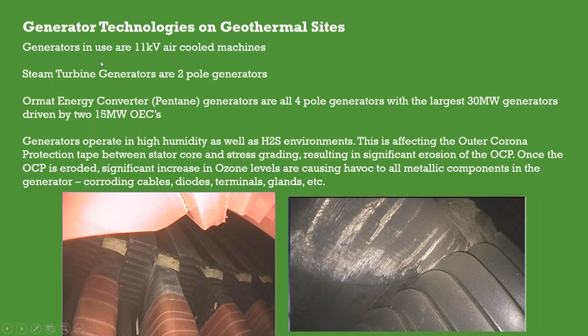The generators used in these geothermal plants are all 11 kV, air-cooled machines. The generators connected to the steam turbines are 2-pole generators, but the pentane OECs, or Ormat energy converters, use 4-pole generators. The largest generator used presently is a 30 megawatt generator, driven by two 15 megawatt Ormat energy converters. These turbines are installed on both ends of the generator, so both the exciter end and what they call the non-exciter end, which I think is better than turbine end or opposite turbine end. Gives the exciter a bit of a nice flavor. But the non-exciter end as well as the exciter end both have a turbine connected to the shaft ends.